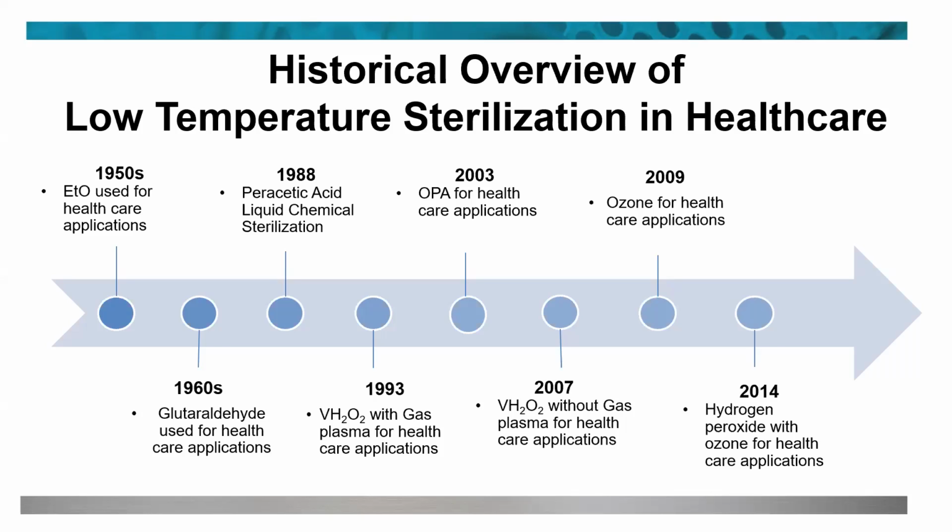In 1993, we see the real first alternative to ethylene oxide become available. The system employed hydrogen peroxide gas plasma to sterilize. It was rapid in the time that it took to process it, and it gave them long-term sterilization. But it was limited to the kind of compatibility it had with materials and instrument length lumens.